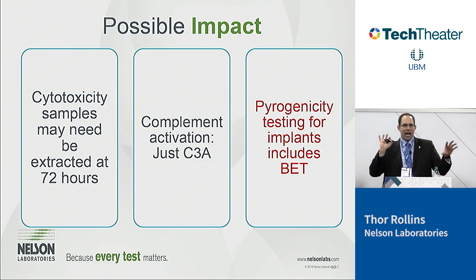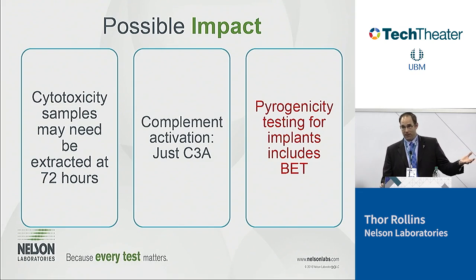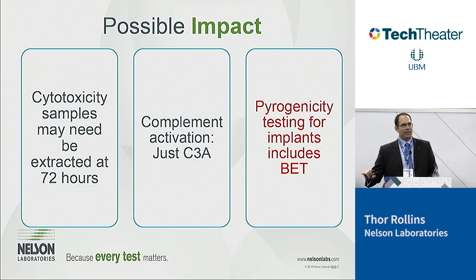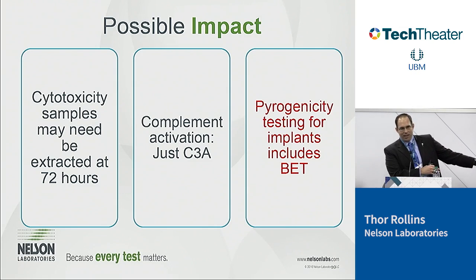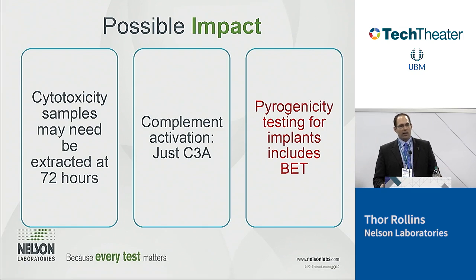So there's really 2 types of things that cause fever. We have something that's called endotoxin that's found in gram-negative bacteria, okay? And that's looked at by using an LAL test, or bacterial endotoxin test. And then we have everything else that could cause a fever. And we kind of screen for that using a rabbit test. Historically, you only ran the bacterial endotoxin test or the LAL test for devices that contact like the eye or the cerebral fluid or the lymphatic system or the blood, the circulatory system, and that's it. And then you ran that rabbit test on everything else.